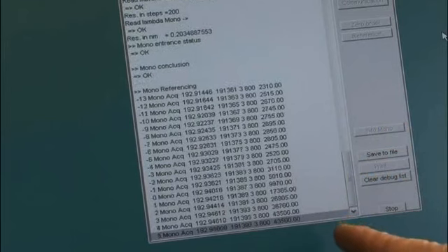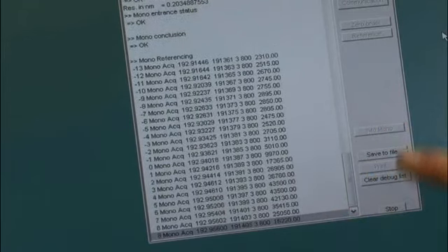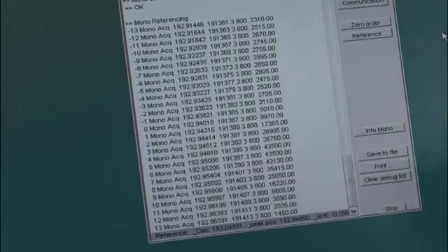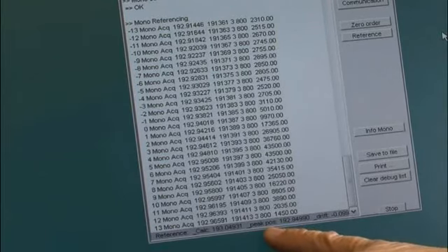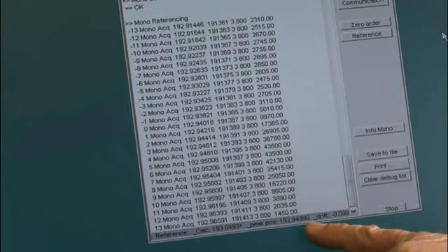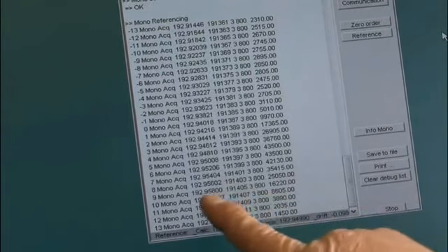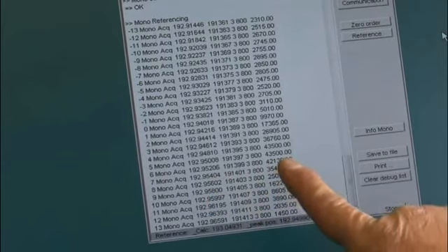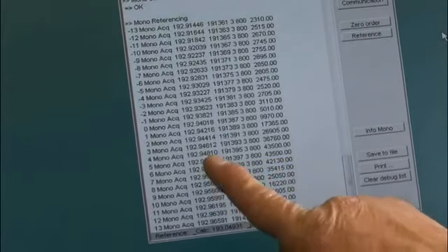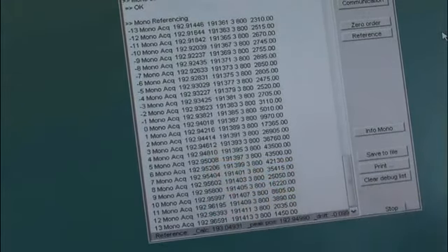As your intensity gets larger, that's when it's coming out over on top of the peak, and then it's coming back down again. So it told me that the carbon peak is 192.949. That should correspond to the highest intensity that we have over here, which basically is right in between these two. So it found the reference line. That's all we need to do on this screen.